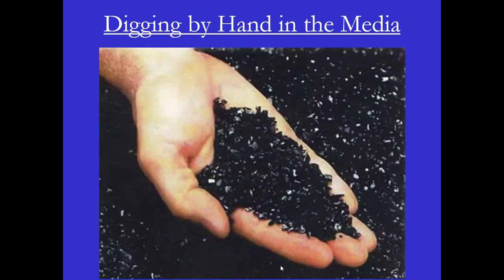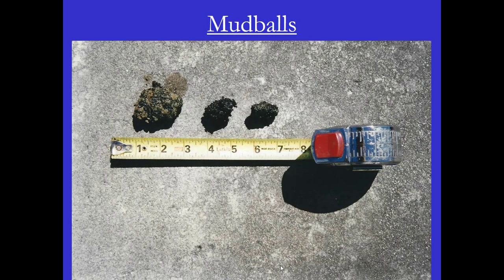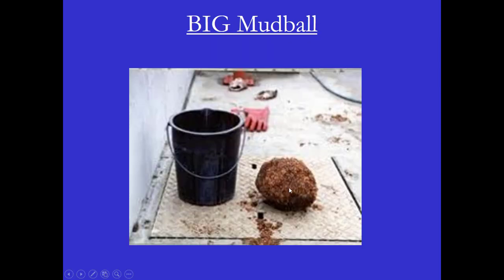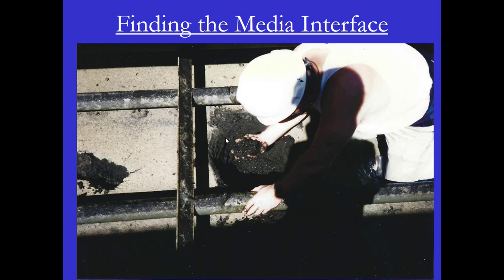Now here's the part I like — getting into a filter and digging into the media. When you dig around, you can find a lot of things. One thing you might find are mud balls — here's a medium size and then smaller ones. However, mud balls can be quite big, as you can see compared to this bucket. Mud balls indicate that the filter is not properly being washed. When inspecting the media, you want to dig down and feel it. Does it feel really slimy? Does it feel like there's a gross overfeed of coagulants? How deep is the top layer of mud? How deep does it go down into the media?